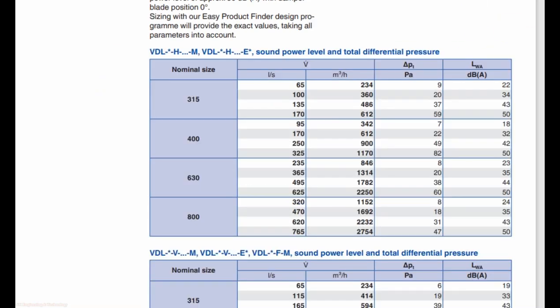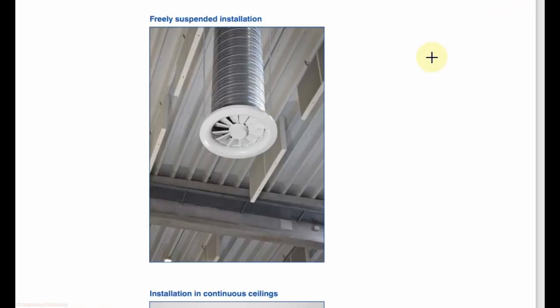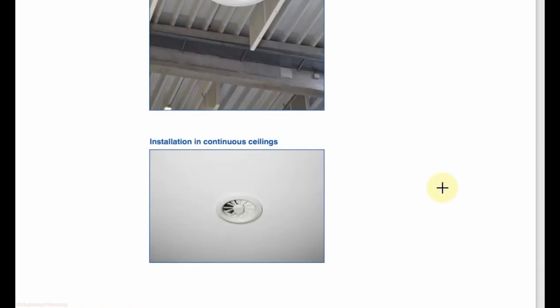To select the swirl ceiling diffuser, there are different tables according to the models. In the table, the first column shows the nominal diameter of the diffuser, followed by airflow in liters per second and sound level. First select the airflow, then check the NC level — if acceptable, finalize; if not, go to the next size. The swirl diffuser can be installed in different ways: with a plenum, freely suspended, or with a false ceiling.